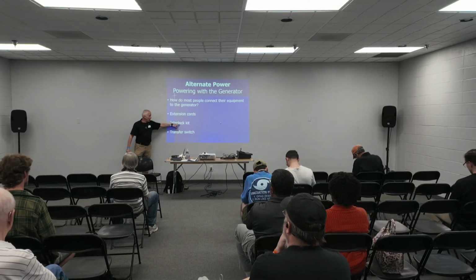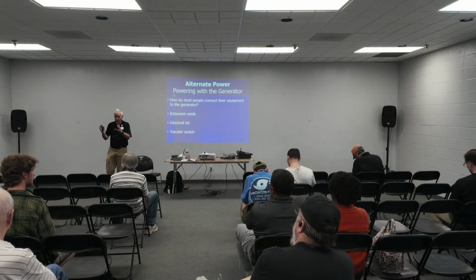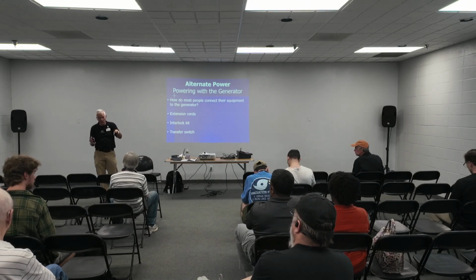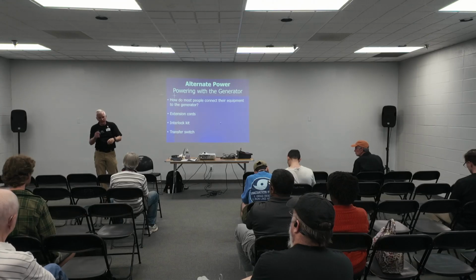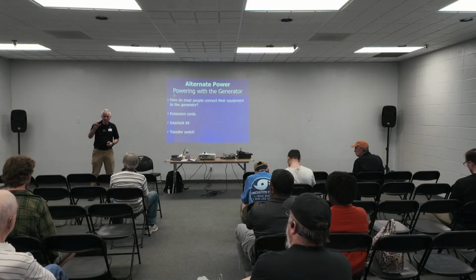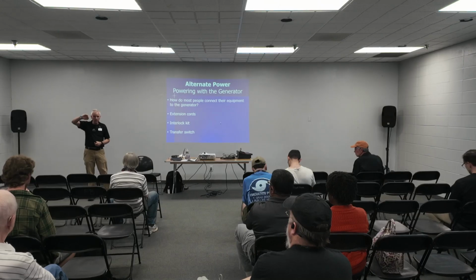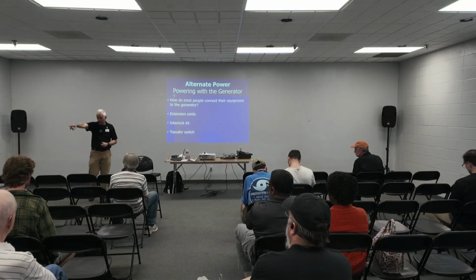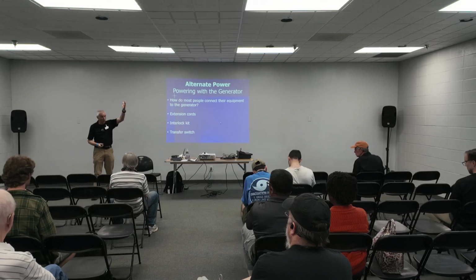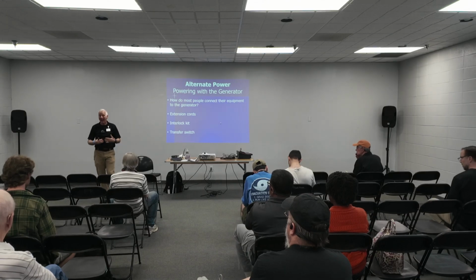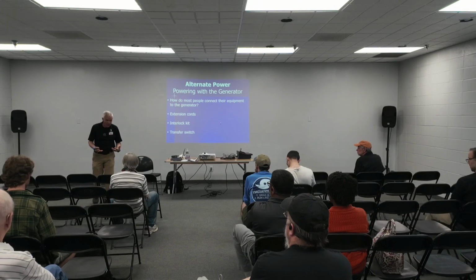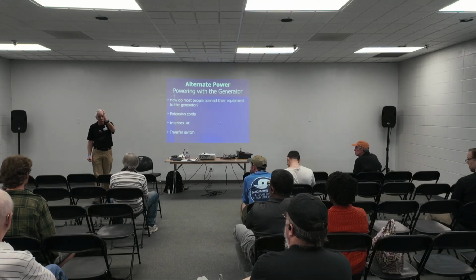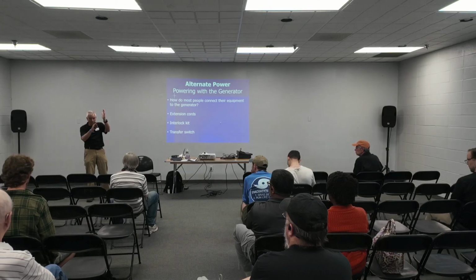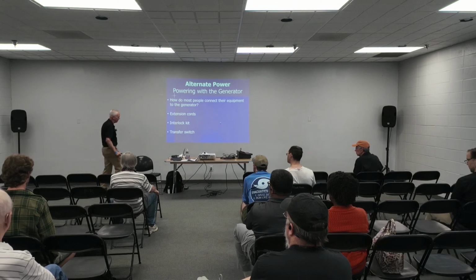An interlock kit is what you were talking about - essentially you put a plug that ties into your breaker box, and there's a switch. You turn your main breakers off - this protects the folks working on the lines, because what you're doing is back feeding your house. The switch moves over, so you can't turn the generator breaker on without turning that one off and sliding that interlock. You can look it up, it's real easy.